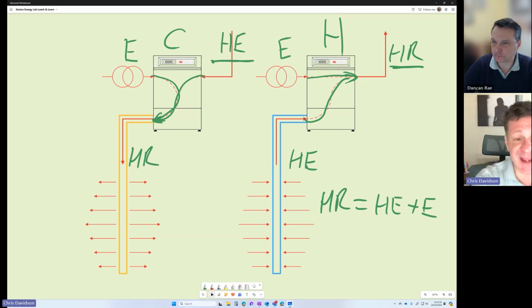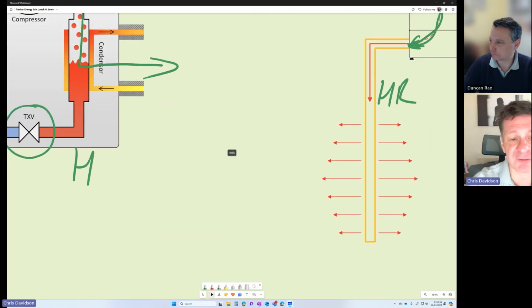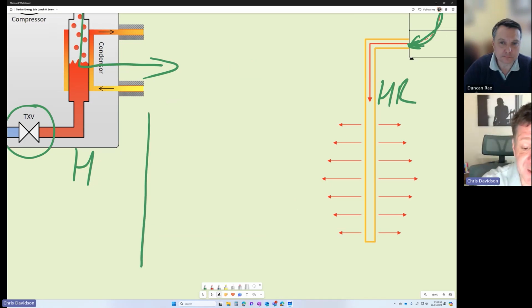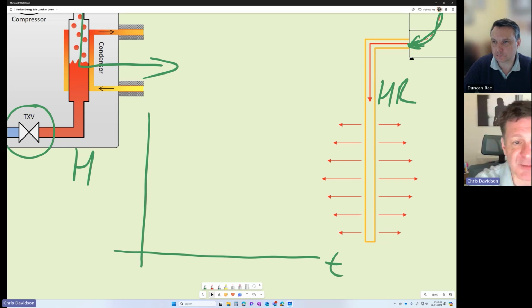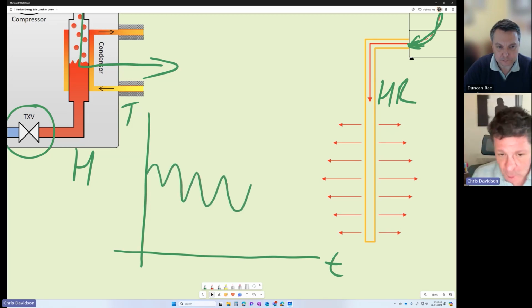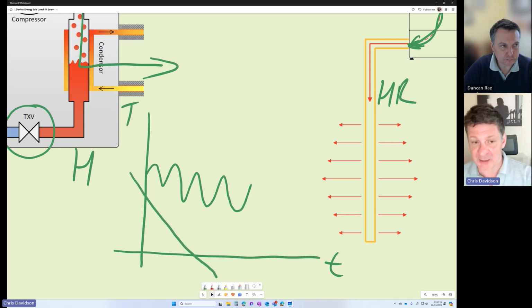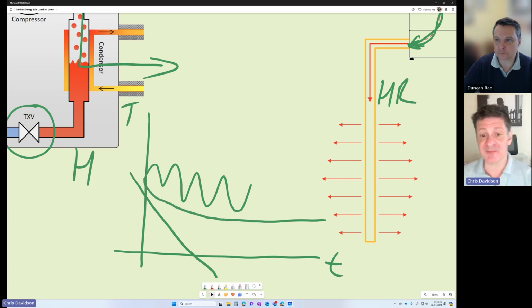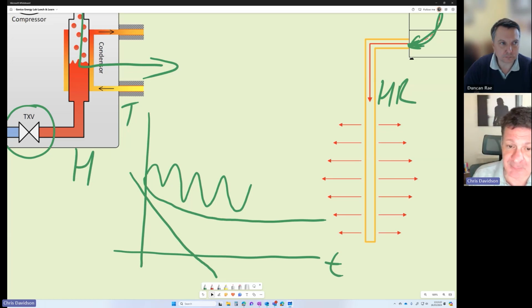Now, what I mean by sustainable in the long term is if we draw a graph of the temperature evolution of that ground loop over time - time down here, temperature of the ground loop here - we'll start at the temperature the ground is at, and each year, each winter, it'll get a little bit colder. But we don't want it to just continue getting colder and colder. That would not be a sustainable system. We want it to level off, or tend to a limit as we'd say in maths, within the effective operational envelope of that heat pump.